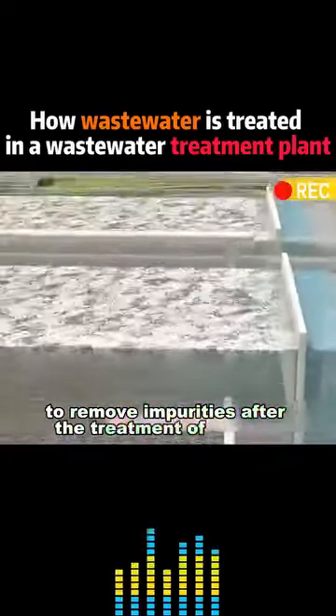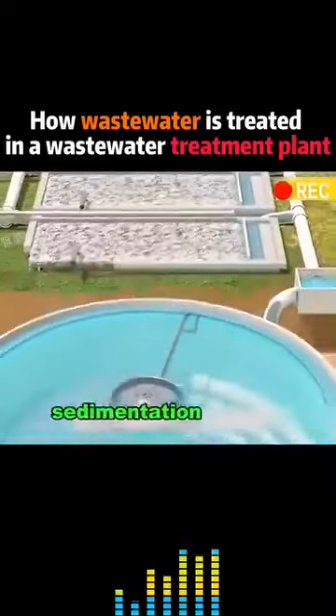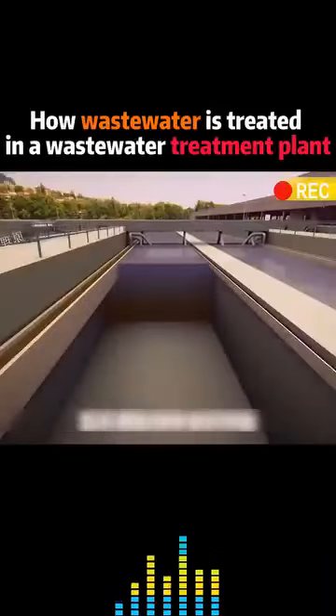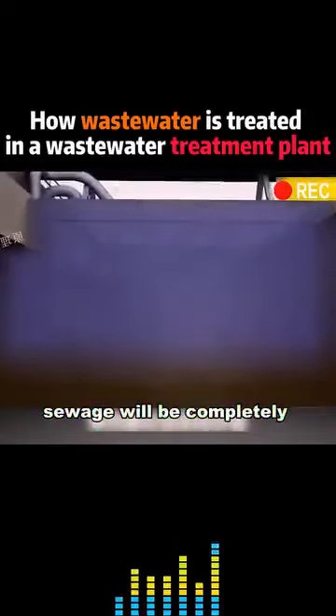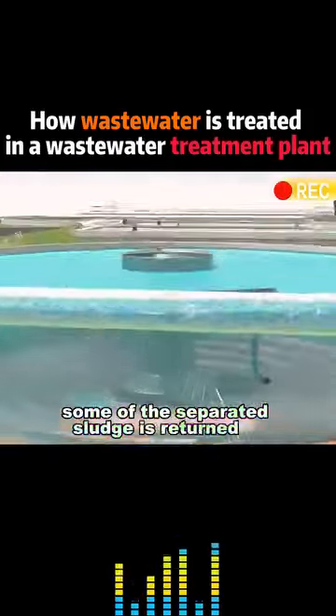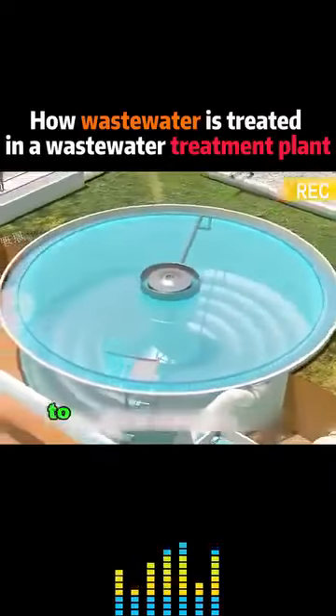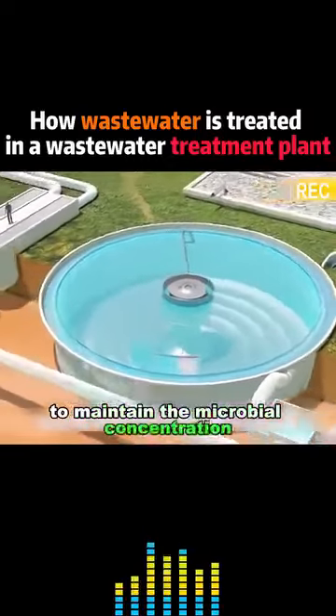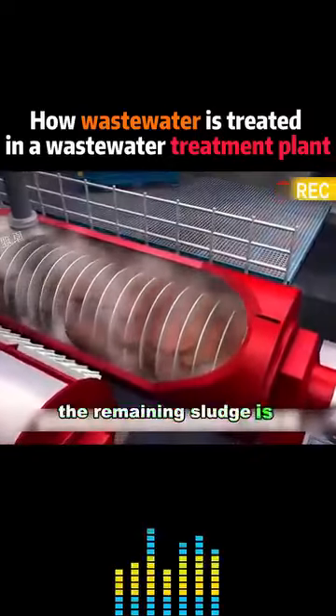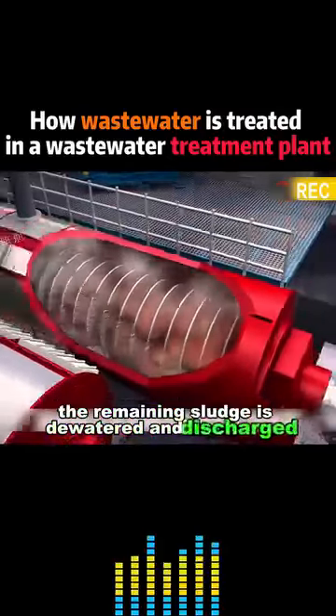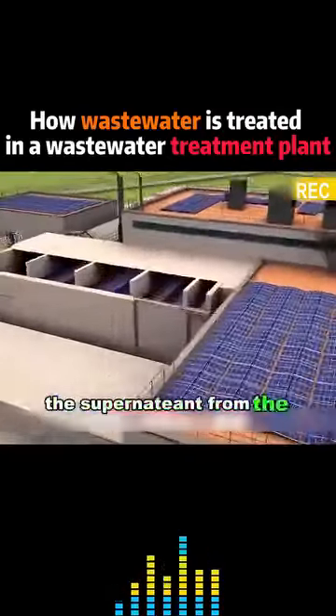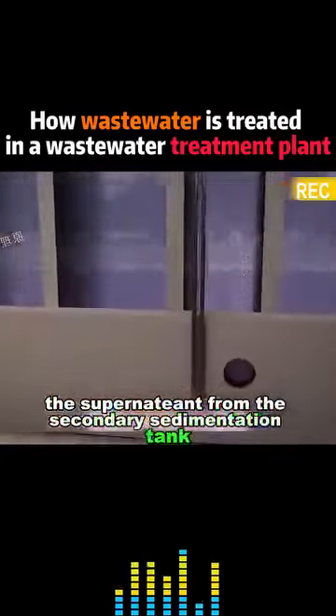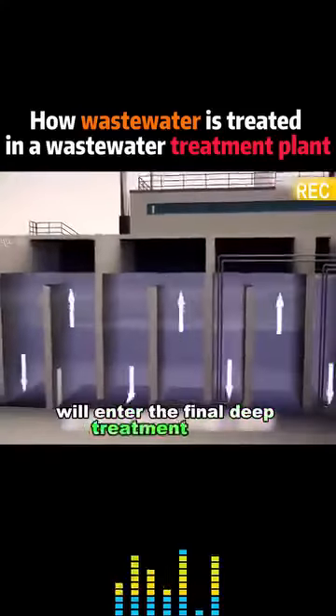After the treatment, the sewage will enter the secondary sedimentation tank for precipitation. At this time, the activated sludge in the sewage will be completely separated from the water. Some of the separated sludge is returned to the biological treatment unit to maintain the microbial concentration. The remaining sludge is dewatered and discharged. Then the supernatant from the secondary sedimentation tank will enter the final deep treatment stage.